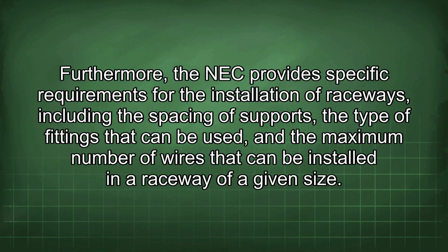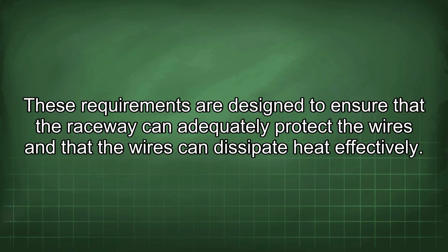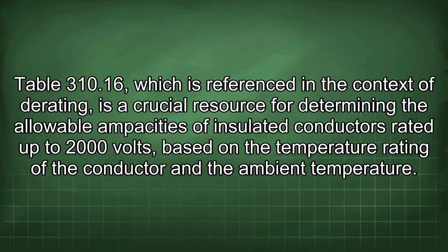Furthermore, the NEC provides specific requirements for the installation of raceways, including the spacing of supports, the type of fittings that can be used, and the maximum number of wires that can be installed in a raceway of a given size. These requirements are designed to ensure that the raceway can adequately protect the wires and that the wires can dissipate heat effectively.